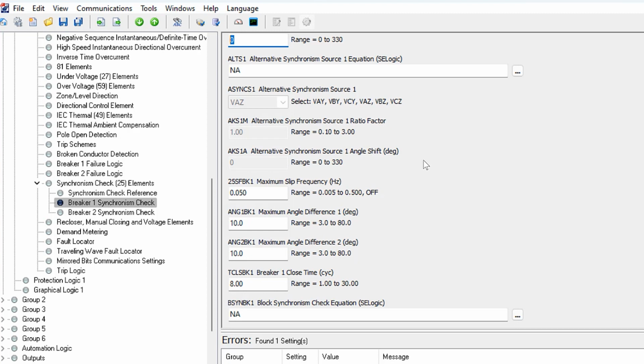Now the relay can compensate for this phase angle difference and the change in those phase angles, and it can account for the time that it takes for the breaker to close after we've issued the close signal. So in other words, the phase angles would be shifting with respect to each other. So if you keep one fixed, the other one is kind of rotating around it. The relay can compensate for that rotation so that it issues the sync check signal, accounting for the time that it's going to take for the breaker to close, so that at the moment that the breaker closes, the two voltages are actually in synchronism.